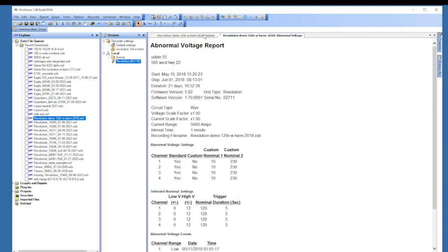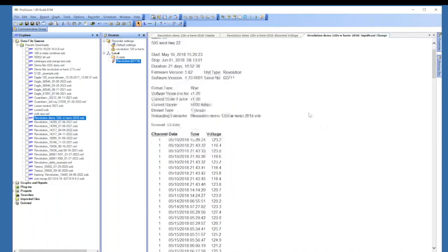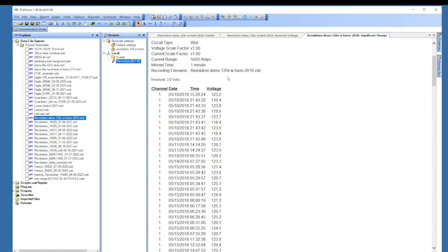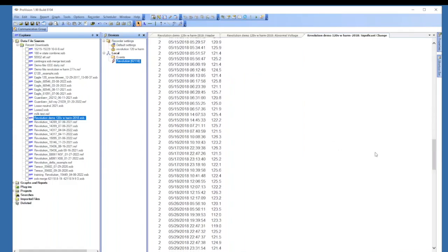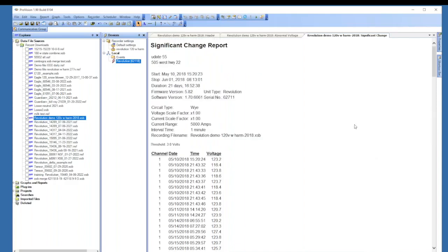I'm going to go back to my header report that's up here, and we'll take a look at significant change. So this was the 3-volt threshold, and you can see right here that you have a 1 second difference. So it went from 116.4 to 123.8. So if someone's complaining about flicker and they actually wrote down times, you could look through here and you see it goes channel 1, channel 2. There is a graph that goes along with that.